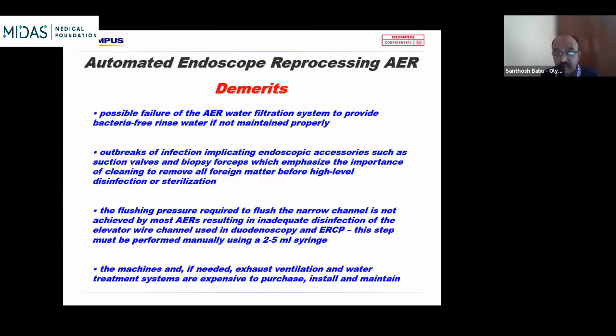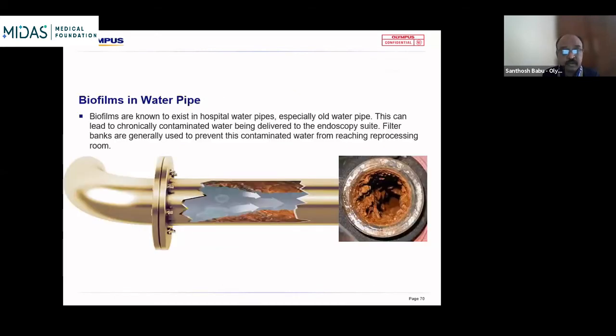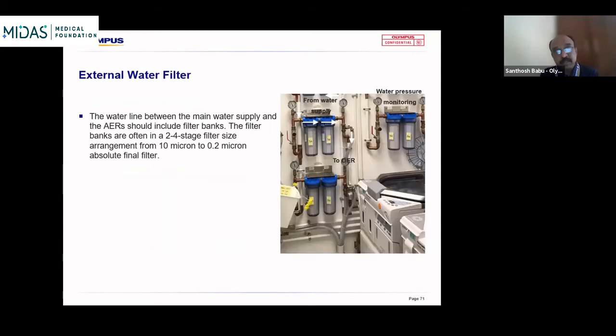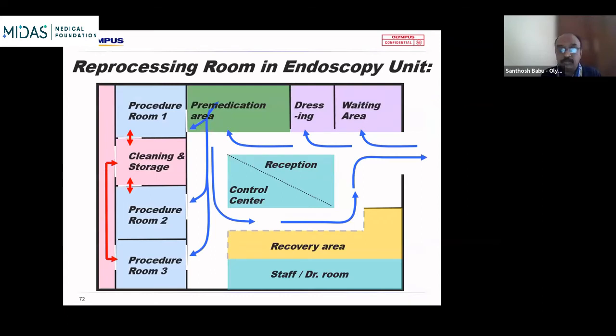Demerits: you have to maintain it. If you've invested heavily in the washer and don't maintain it, then it's back to square one. Biofilms are a huge issue, so you have to take care of biofilms in the hospital water line. We install pre-filters like these so that before water gets into the washer, you filter it and give clean water to the reprocessor. In the reprocessing room, ideally, the blue line shows the movement of the patient, and the red line shows the movement of dirty equipment.